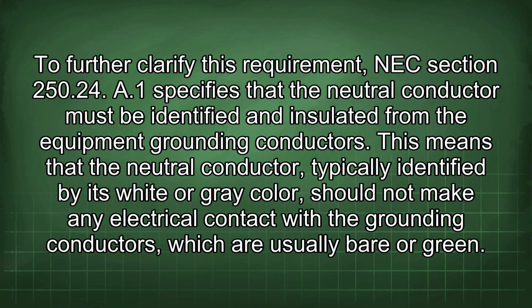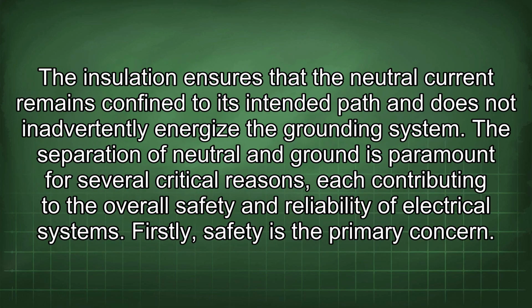To further clarify this requirement, NEC section 250.24(A)(1) specifies that the neutral conductor must be identified and insulated from the equipment grounding conductors. This means that the neutral conductor, typically identified by its white or grey color, should not make any electrical contact with the grounding conductors, which are usually bare or green. The insulation ensures that the neutral current remains confined to its intended path and does not inadvertently energize the grounding system.